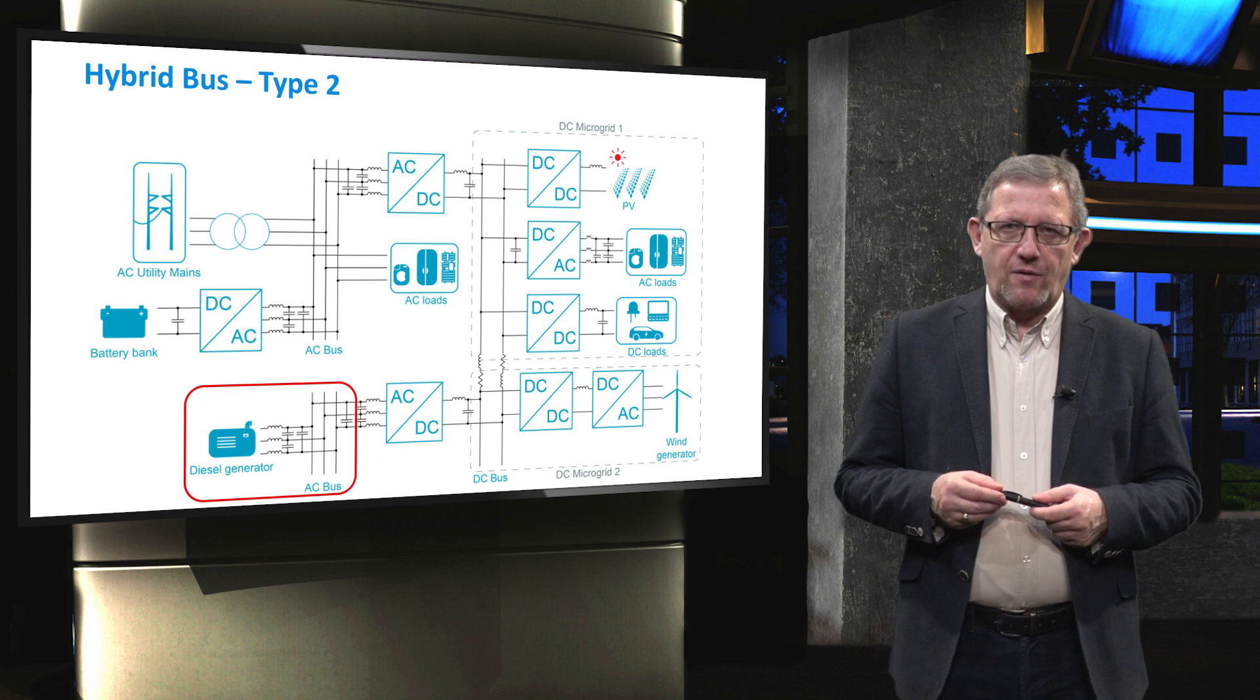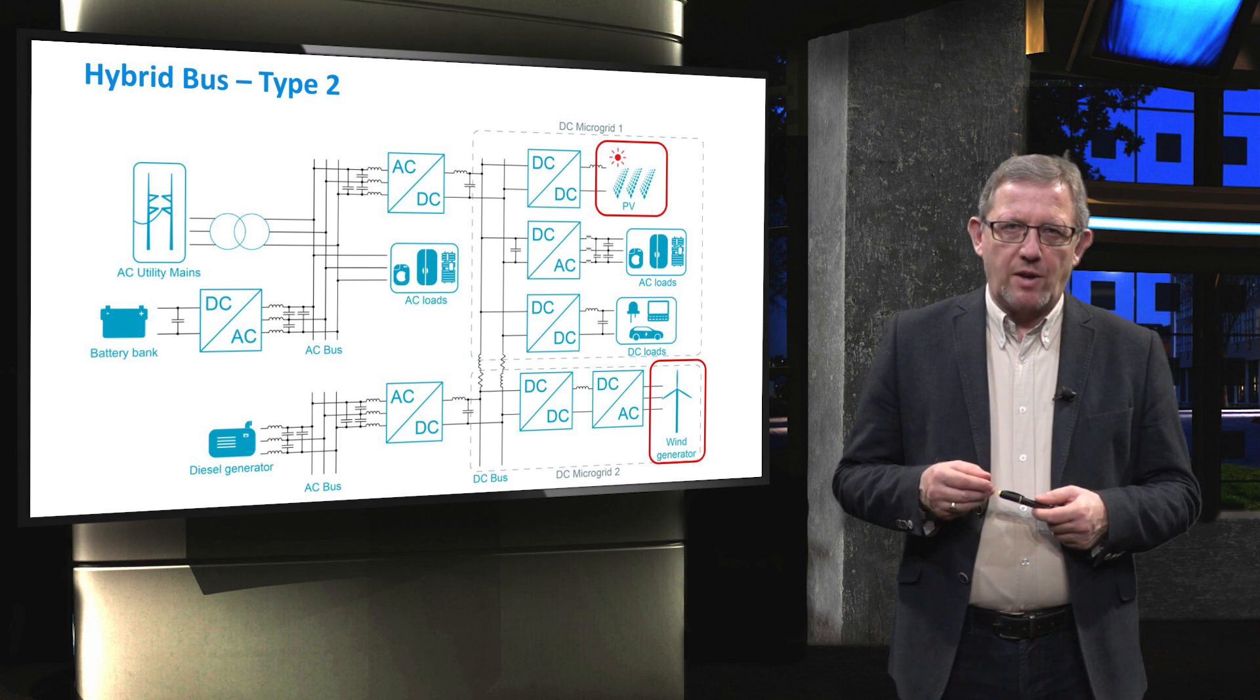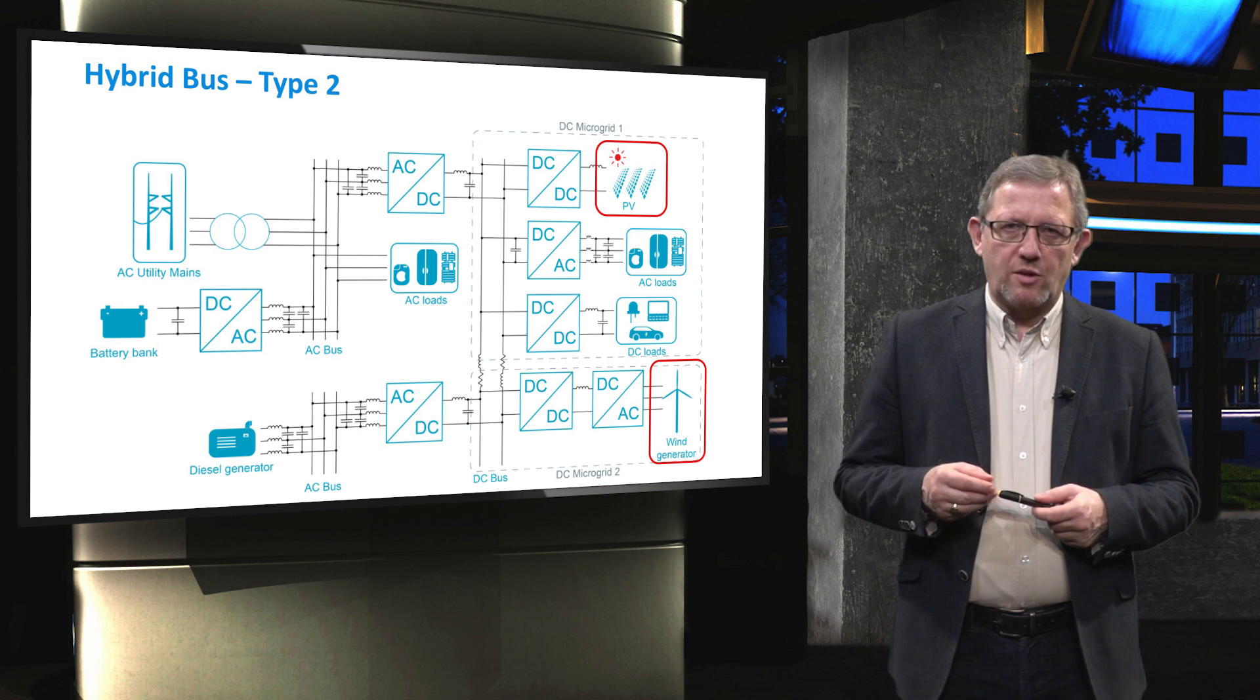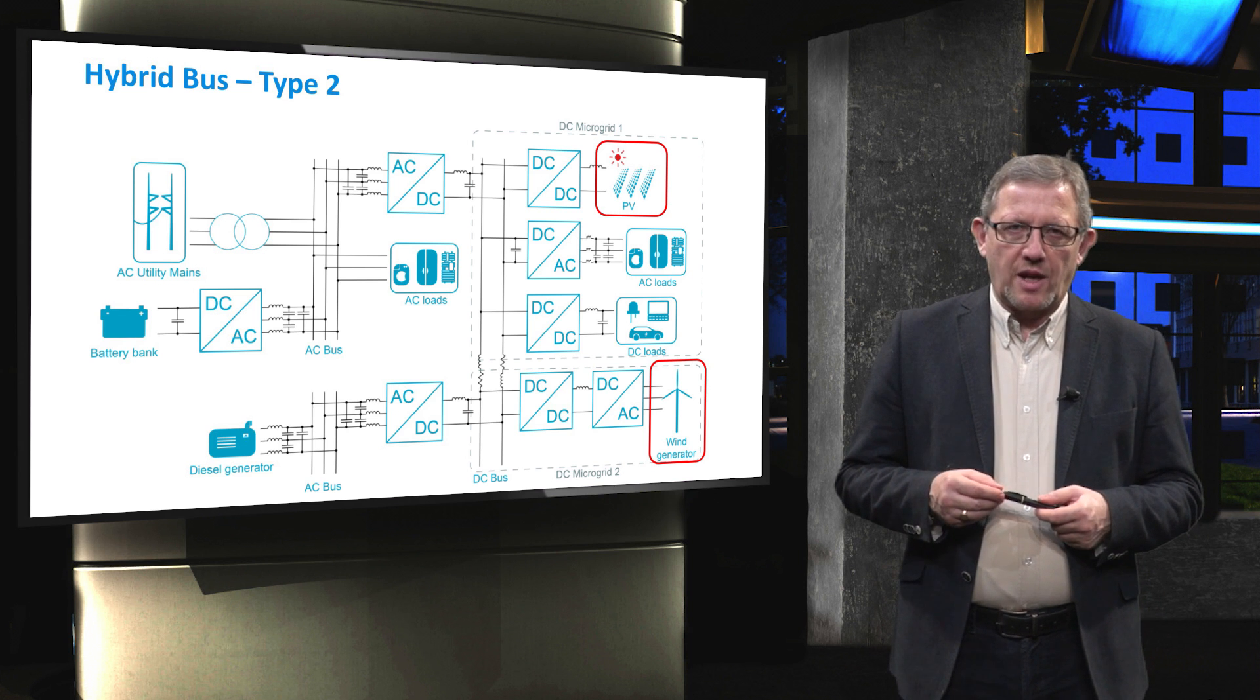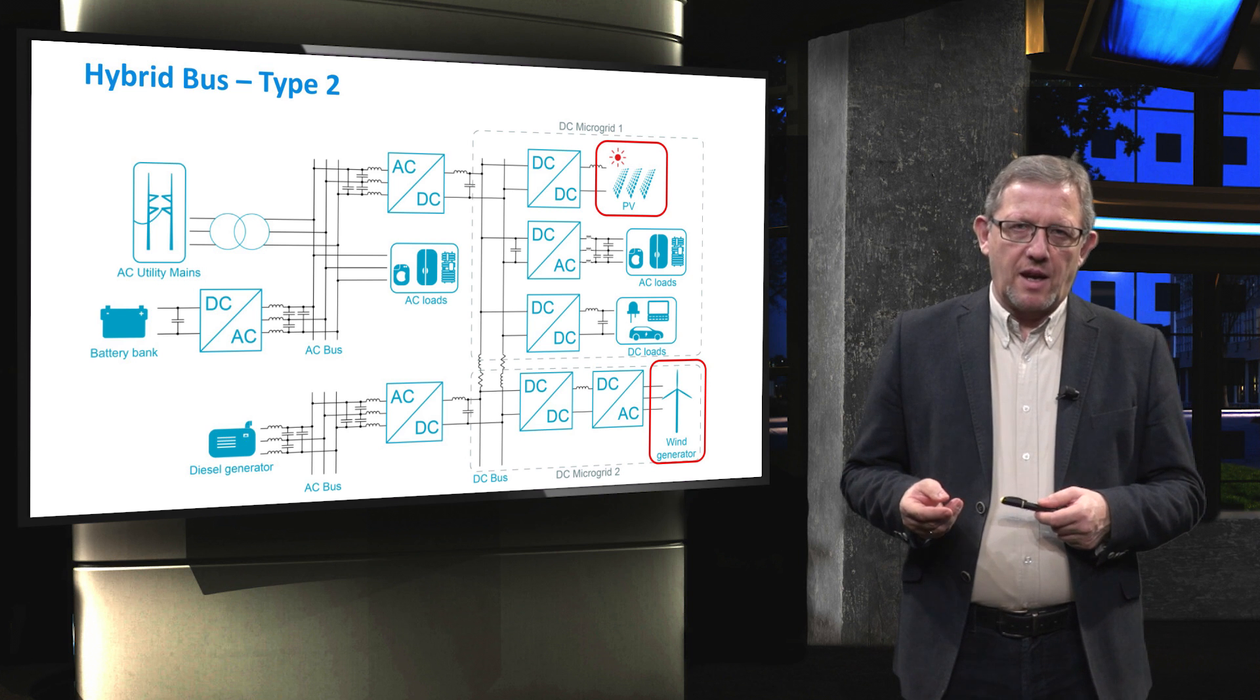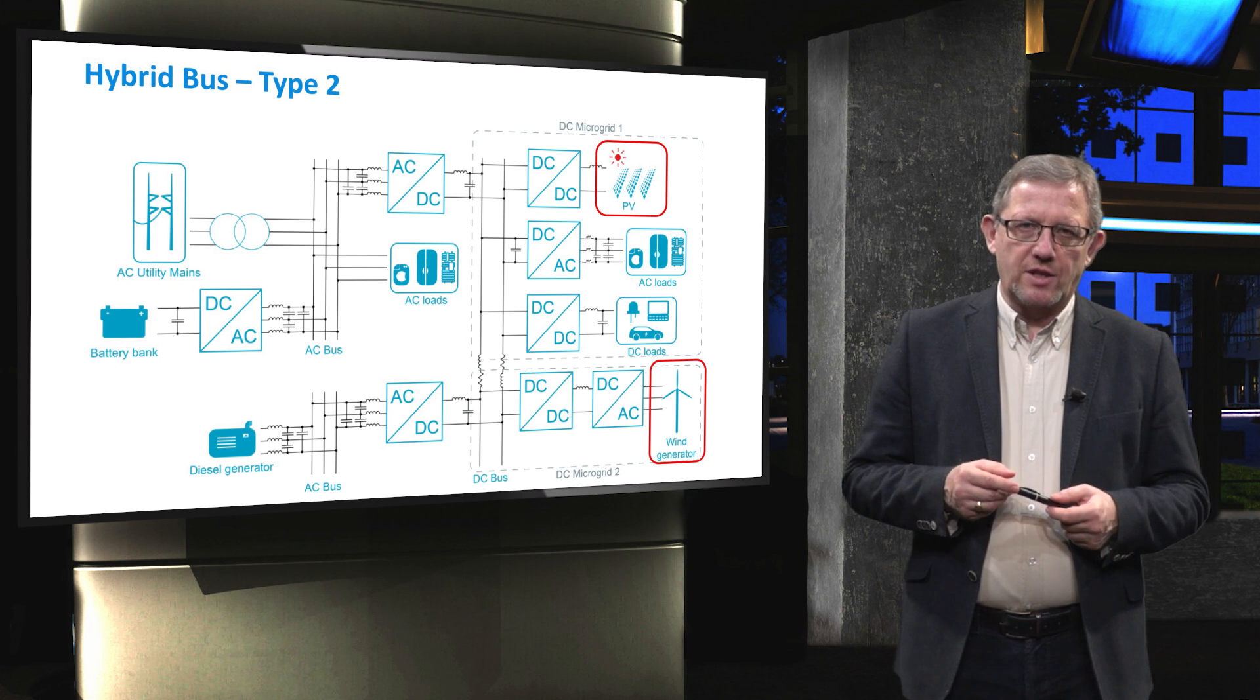The power generated by the diesel generator can effectively mitigate the intermittencies associated with wind and photovoltaic solar at the DC bus and can be exclusively and directly consumed by the loads connected to the DC bus. This might result in increased efficiency where particularly during high prices the power generated by diesel is not first stored in the battery and then sent to the DC bus, avoiding charging and discharging efficiency losses of the battery.